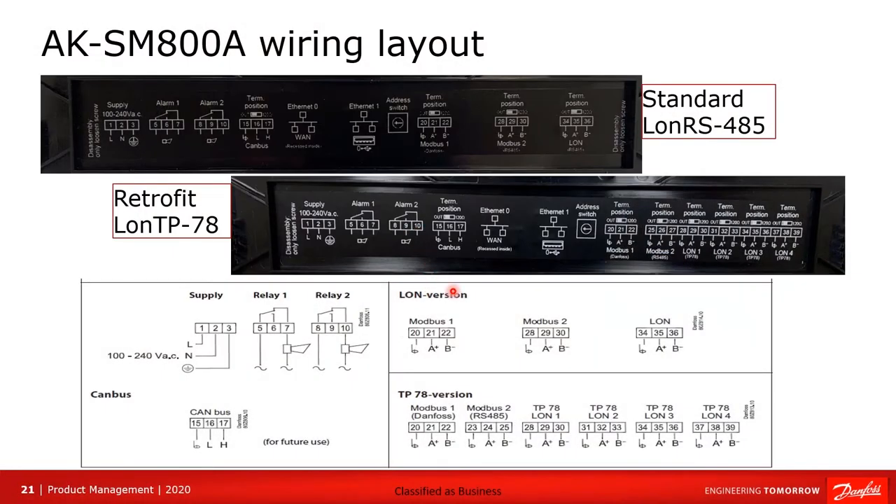If you remove the blank plate over the connections and flip it over, you'll see a clear indication of all your connections. Going across: supply alarms, CAN bus, MOD bus, MOD bus 2, and LON — with clear indication of polarity. You must honor polarity here.